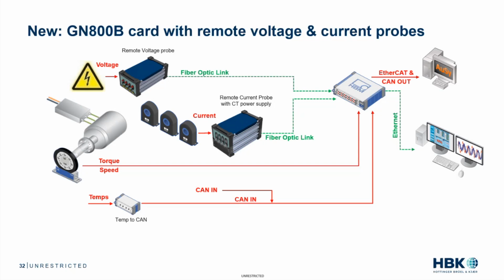And then instead of having that extra power supply and extra cabling to power the CTs, here we've got the actual CT power supply built into the remote current probe. And you can connect the CTs directly to this remote current probe. And both of these probes, voltage and current, are providing the measurement results back to the power analyzer via fiber optic. So now you've eliminated a lot of the high voltage issues back in your lab, the control room, I should say. And then also you have basically isolation and EMI mitigation with this setup, resulting in minimizing or conquering the EMI issues.